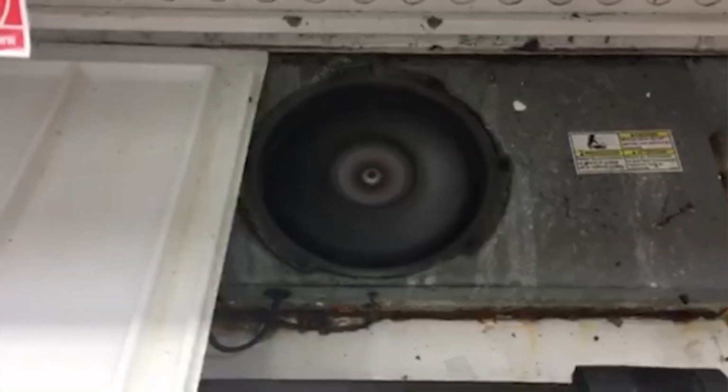The second major issue is that fan sucks air in and blows it up the back of this ductwork. I just had them pull on. Oh, check out the dent. Because they caved in the ductwork up top here, and if you look down, it's vacant. Surprise! I don't know why it's sweating.